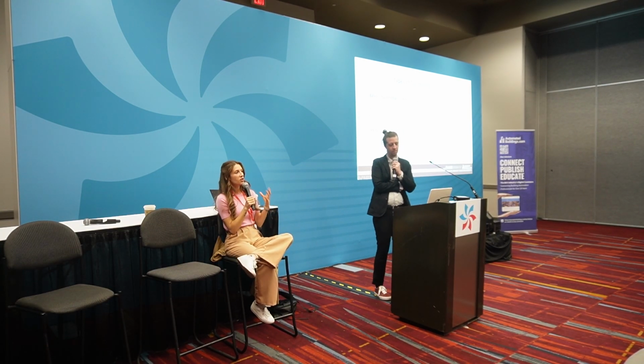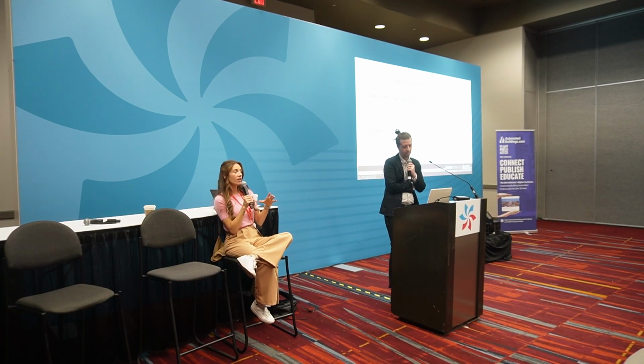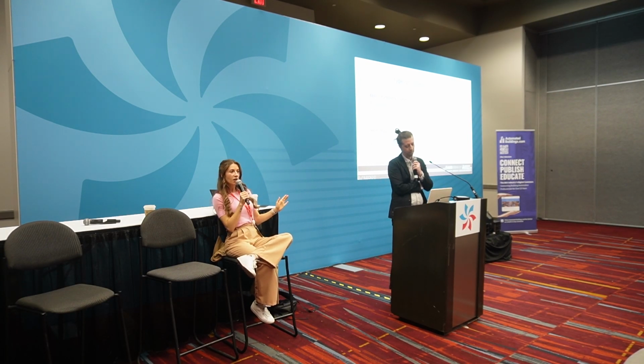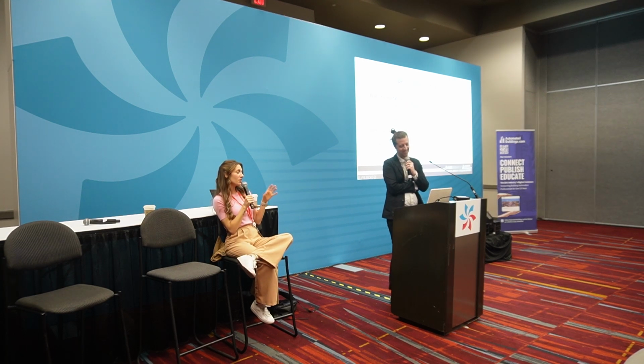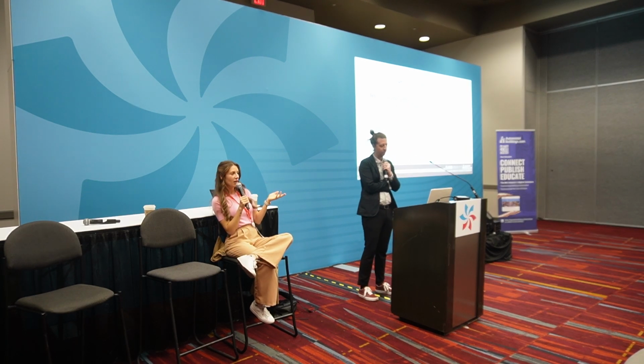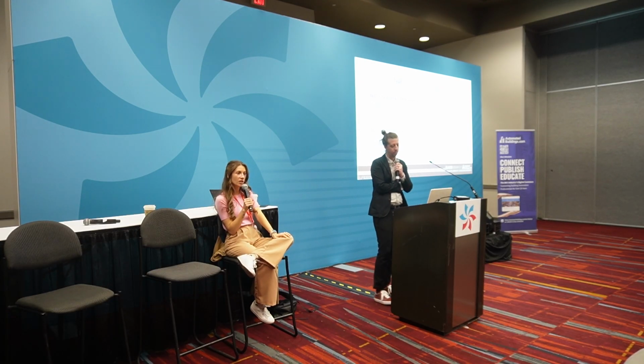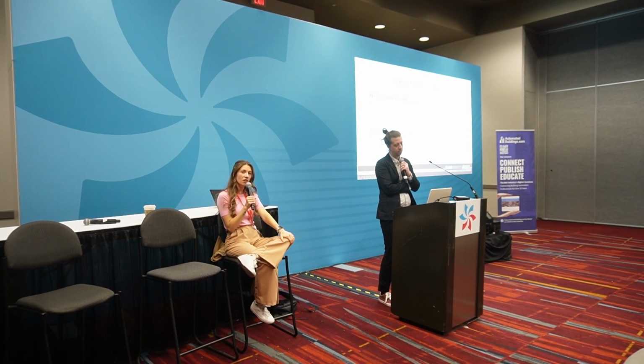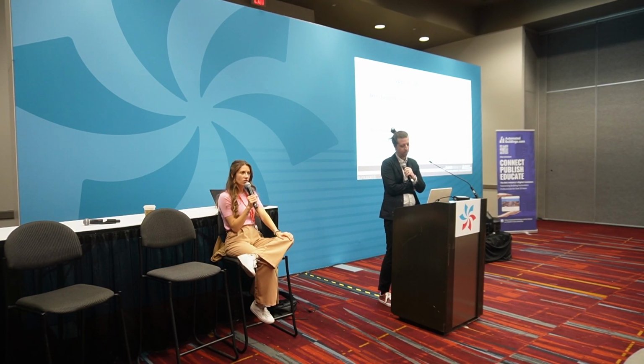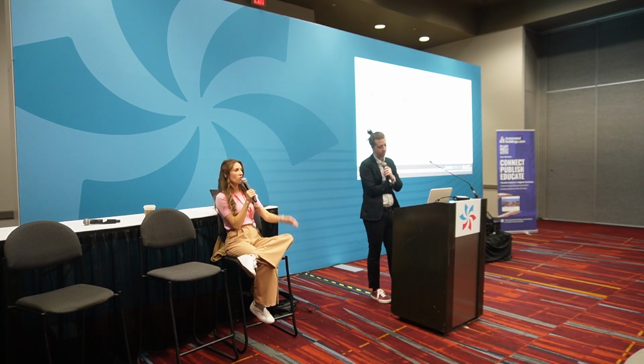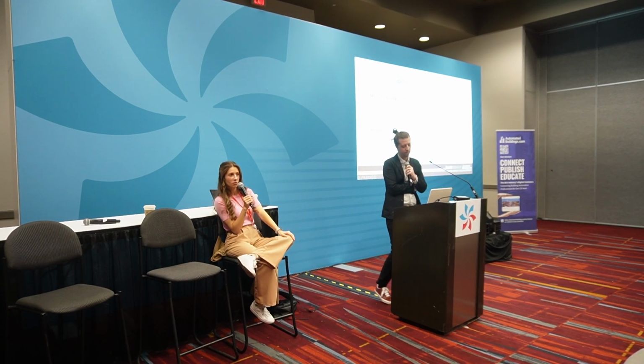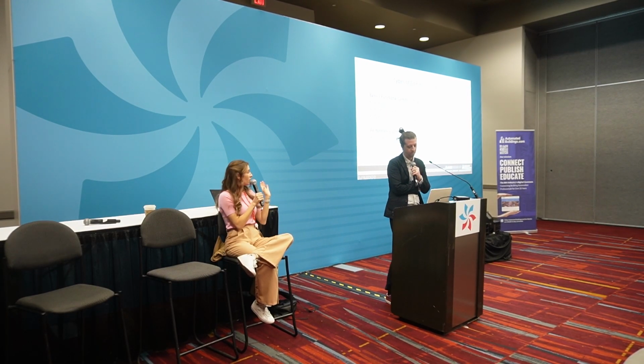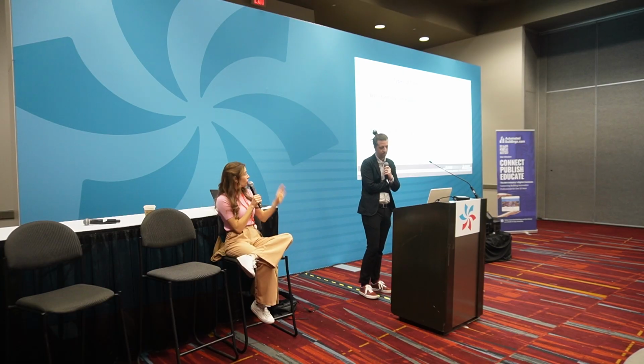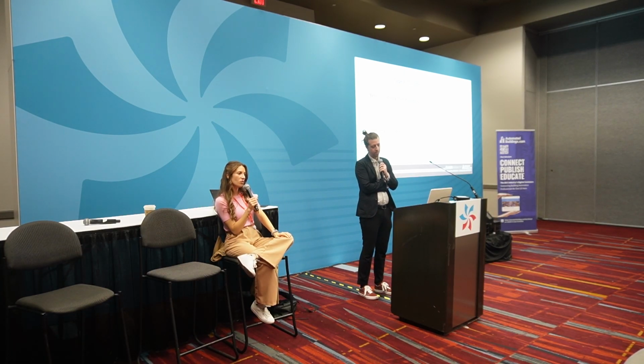That performance commissioning piece is often not common. Not to broadly generalize, but almost every time we go into a system — and this happens a lot, I'd say 25-30% of our work at this point — it's: hey, we have this building, we installed this new VRF. Hey, we have this LEED Platinum building, we're using way more energy than we should, or this has never actually worked. We installed this solar thermal and we've never turned it on because it's never really worked. So it's a lot of that, and almost always it's a result of improper or complete lack of performance commissioning — not the functional check piece, because that really does get done most of the time.